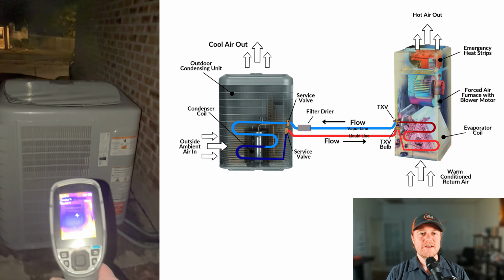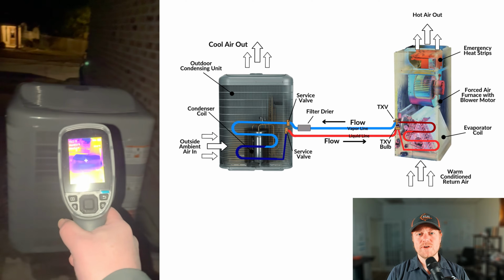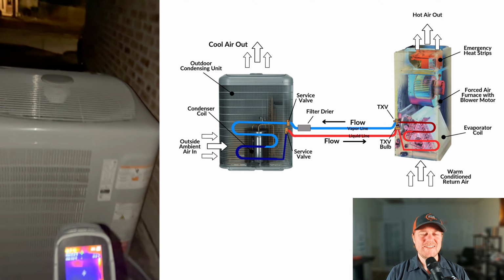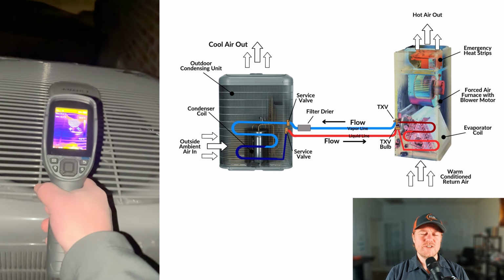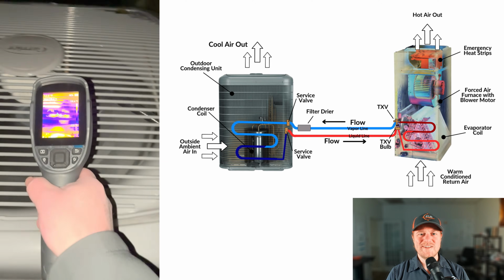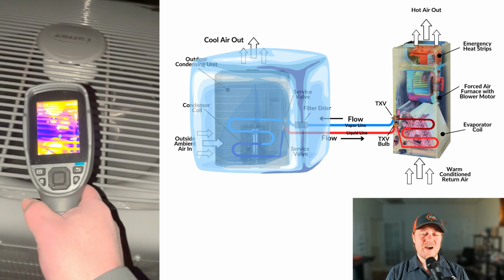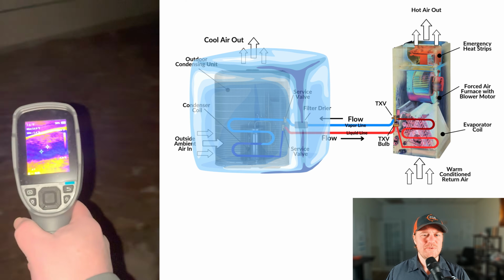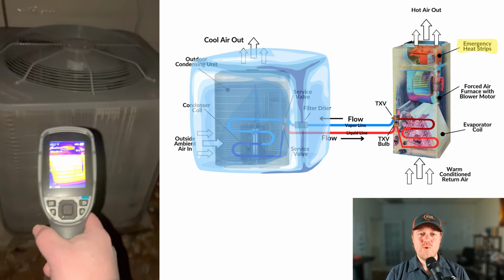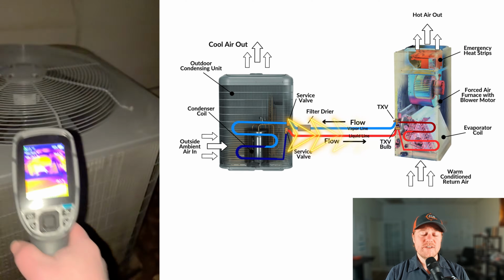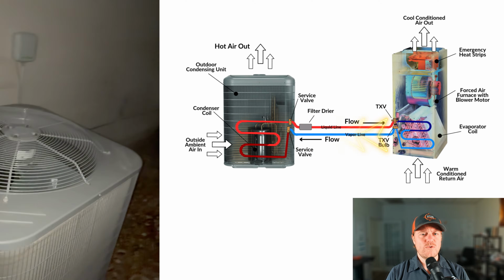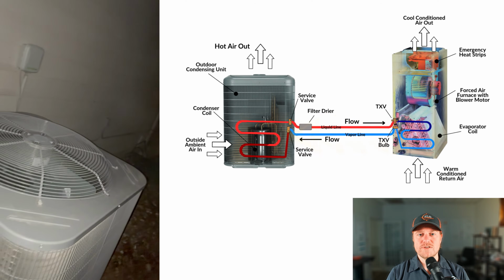Now, if a heat pump is trying to pull heat from outside and it's a really cold day, like on this day here, it's 18 degrees outside, and my thermal gun is showing that the condensing coils are at 10 degrees, the system is going to start icing up. Once the heat pump ices up, it's not going to be able to heat. So, how do we solve this problem? One way to do this is to reverse the refrigerant flow and turn it back into an air conditioner.